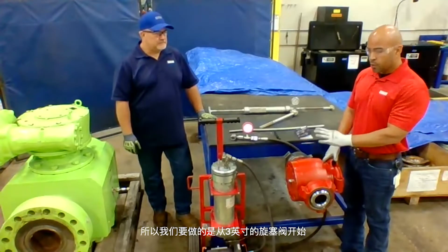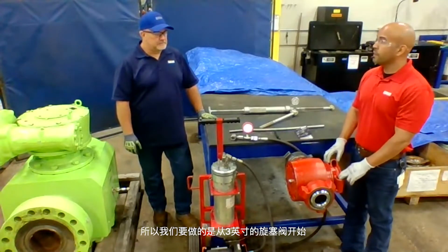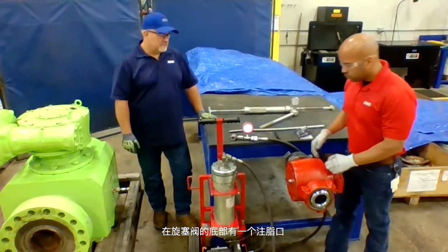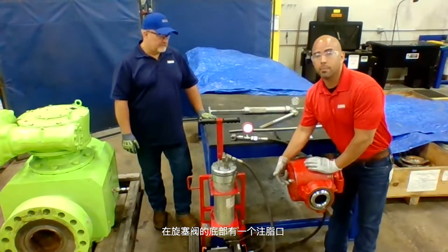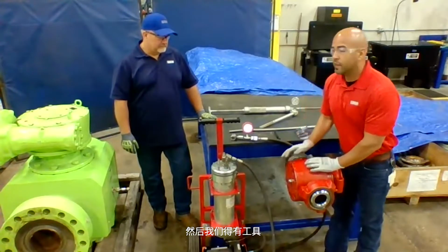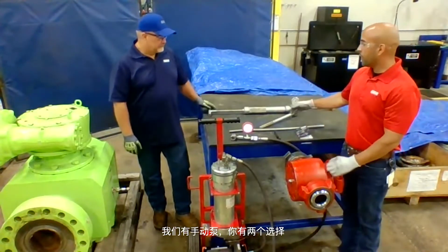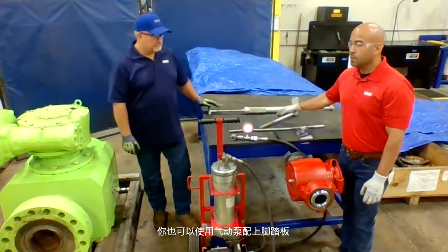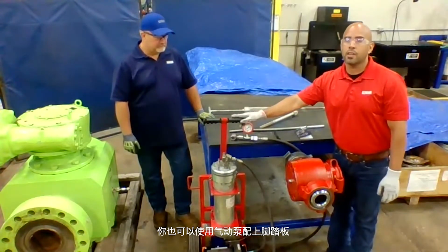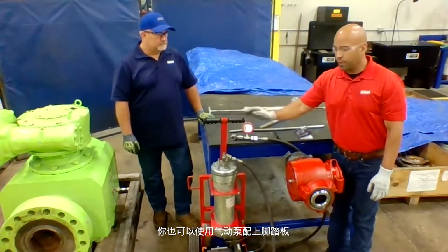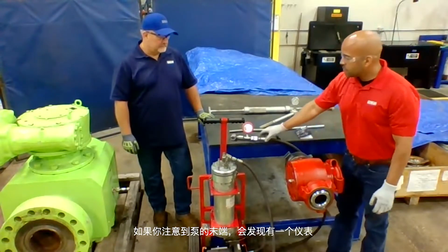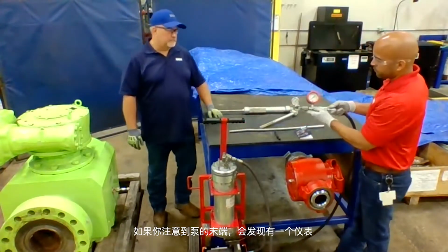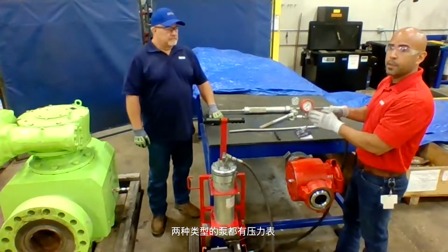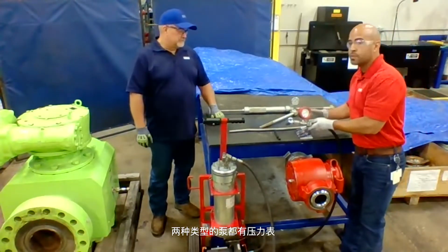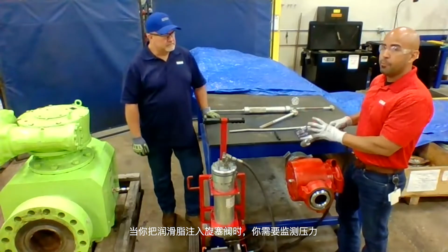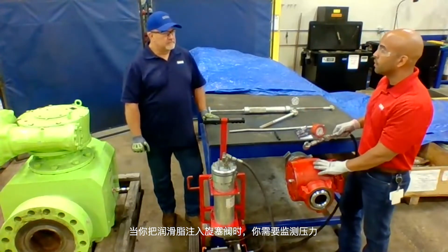So what we'll do is get started on the 3-inch plug valve. We've got a greaser right here on the bottom of the plug valve, and then we have our tools. We've got our hand pump, so you've got two options, and then you've got an air actuated pump that you can use as well with the foot pedal. If you notice here at the end, we've got a gauge. You've got gauges on both styles of pumps, and you're going to want to monitor that pressure whenever you're pumping grease into the plug valve.